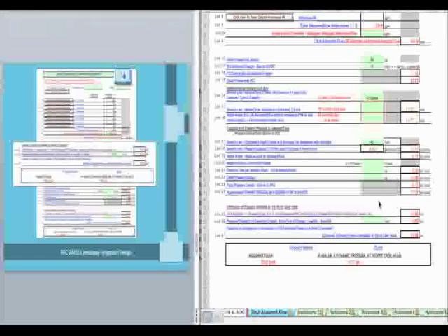So if we go back to our worksheet and we enter right here 22 feet, which is given to us, it adds that pressure loss due to elevation, or subtracts it, I should say, because it's higher than the point of connection, and we end up with an estimated dynamic pressure at the worst case head of 42.15 psi. So down at the bottom of this total assumed flow worksheet, you would have all of that information. So very similar to the metered municipal worksheet, with the added utility of adding hydrozone information.